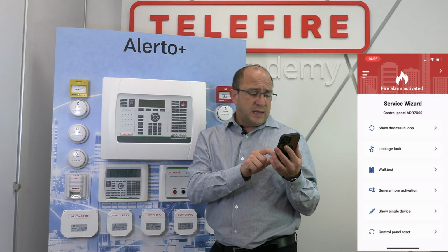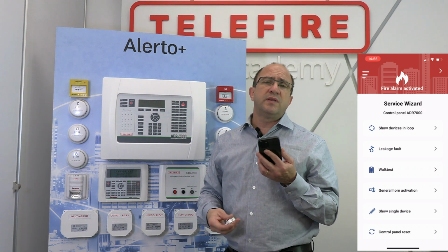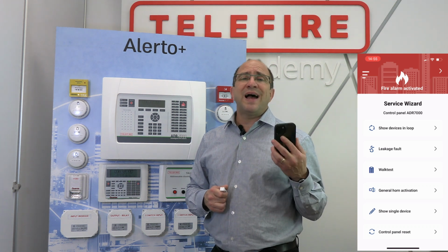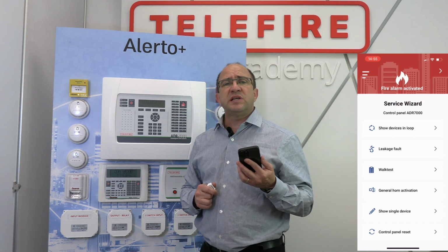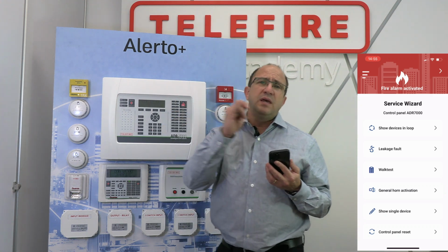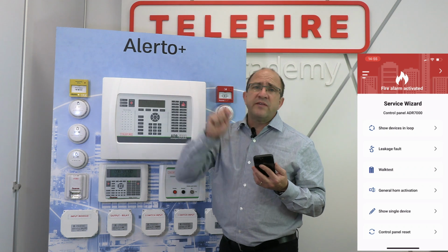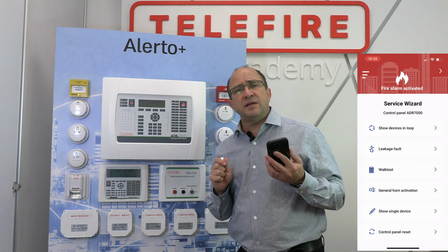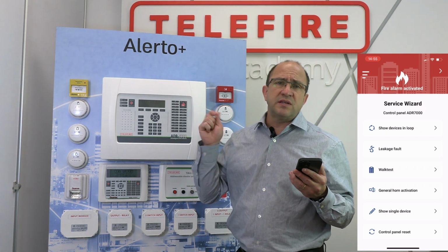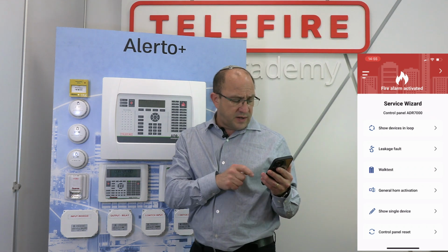What else? Every strobe or horn that is connected to an output and is programmed as a horn, I can activate it and it will be activated for 10 seconds. So when I do a walk test in the factory or the building or whatever, all the sirens will carry on working for 10 seconds. And like that, I know that the sirens are working perfectly.